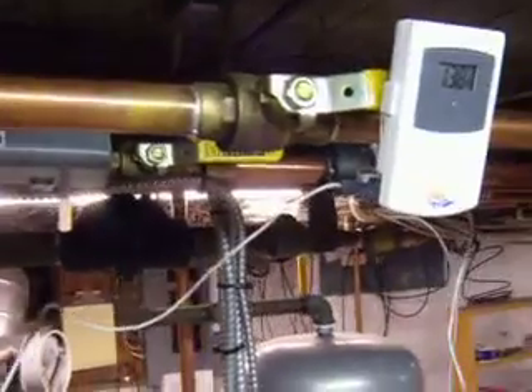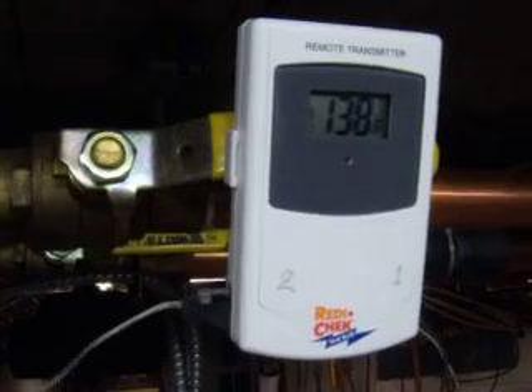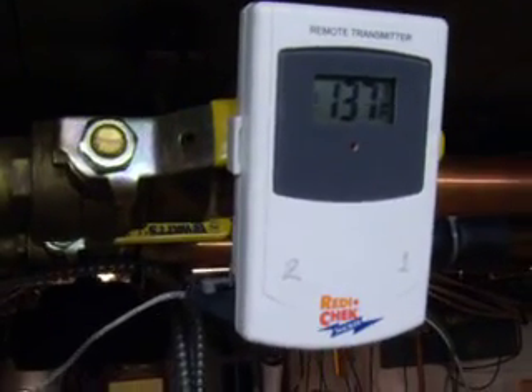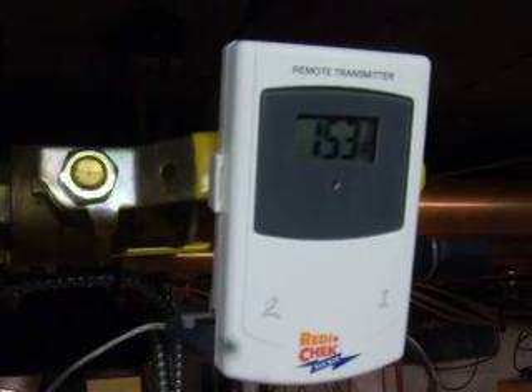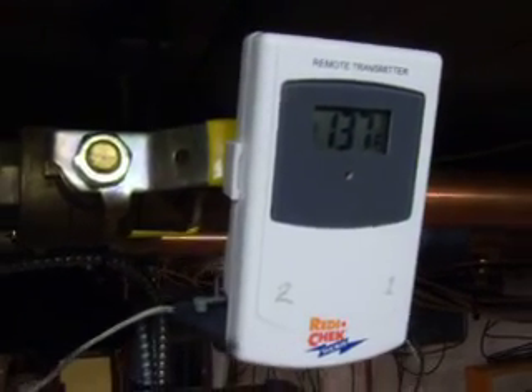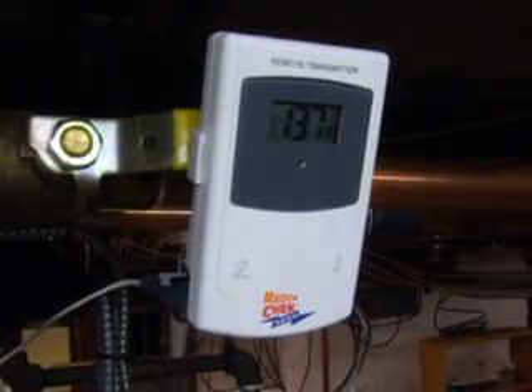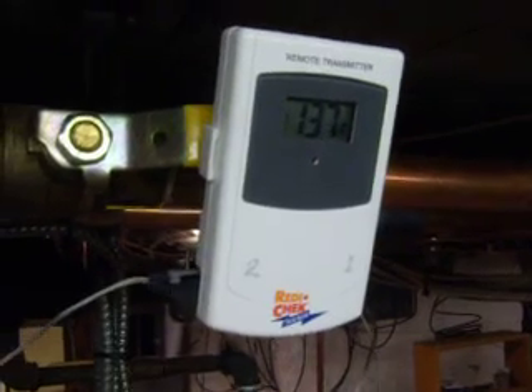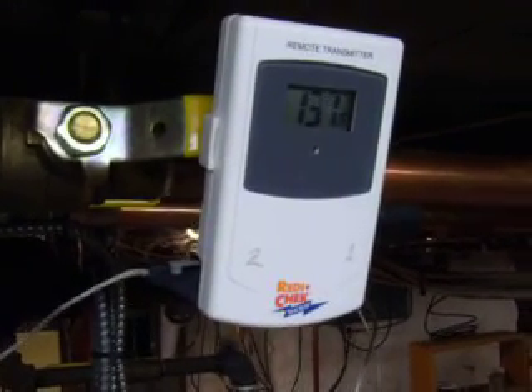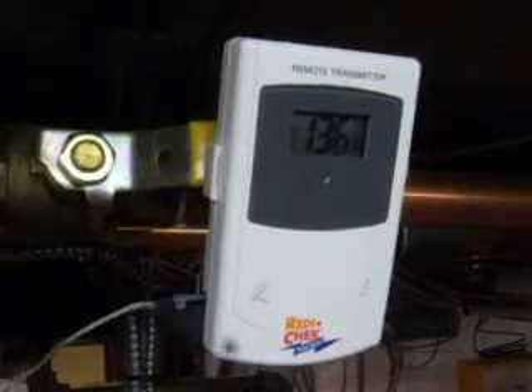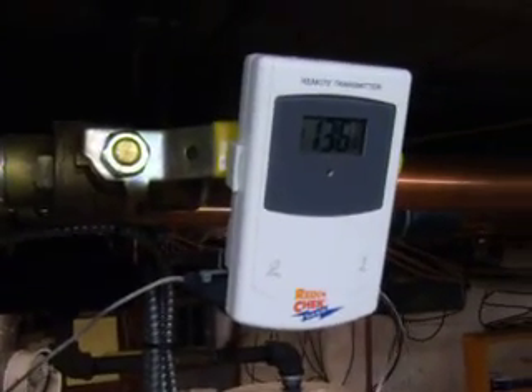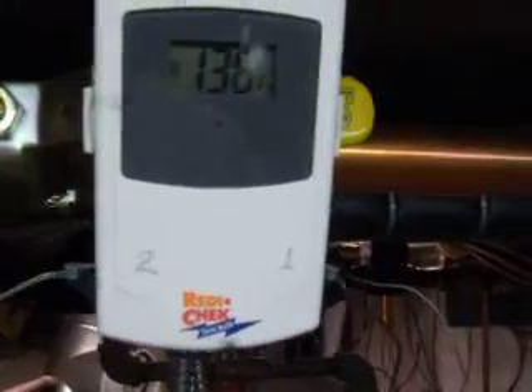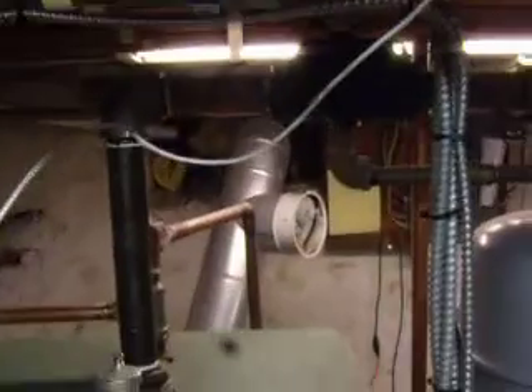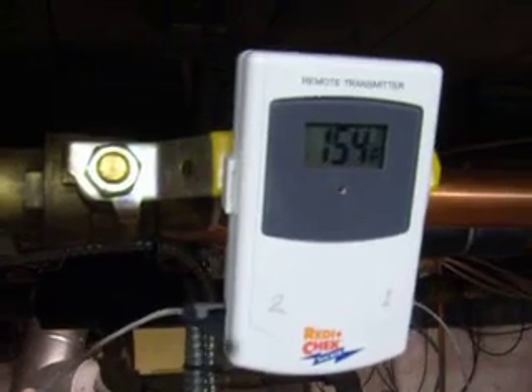A couple extra niceties. This is a Redi-Chek smoker thermometer. It's a remote thermometer, and what it's doing right now is it's bouncing back and forth. I've got 153 degrees coming in, and I have 137 degrees going back out to the boiler. Keep in mind there's a Danfoss mixing valve on the boiler that mixes that 137 degree water with some of the 154 degree water and keeps it at 140 going into the boiler. That again is another thermal protection on the boiler. But what it's telling me is I've got 154 coming in. It's heating my internal components on the oil boiler, and it's sending 137, 136 back outside.